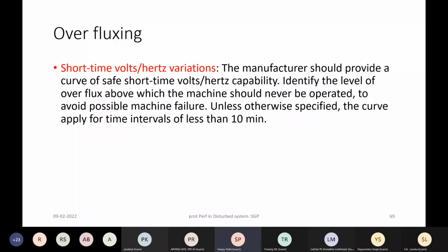So this is one of the risks during system disturbance condition when isolation takes place for any area, and if the area happens to be exporting reactive power after disconnection, this area may experience over voltage condition. Opposite to this is if one particular area is importing reactive power from other region and the disconnection takes place, then this region will be in short supply of reactive power, and then there will be under voltage condition.